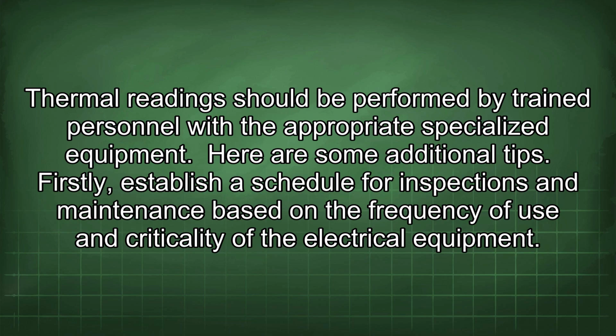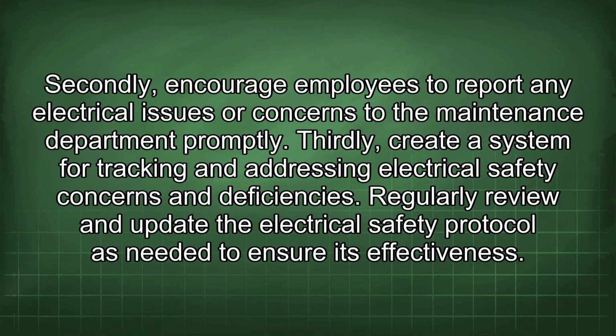Here are some additional tips. Firstly, establish a schedule for inspections and maintenance based on the frequency of use and criticality of the electrical equipment. Secondly, encourage employees to report any electrical issues or concerns to the maintenance department promptly. Thirdly, create a system for tracking and addressing electrical safety concerns and deficiencies. Regularly review and update the electrical safety protocol as needed to ensure its effectiveness.